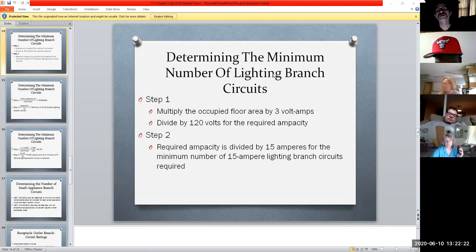So they have steps. Our big takeaway from this chapter is how we determine the minimum number of lighting branch circuits within our house. Our first step: we multiply our occupied floor area by 3 VA. If we have a 1,200 square foot house, we multiply it by 3 and come up with 3,600. We divide that by 120, which delivers our required ampacity. Step 2: we take that number and divide by our 15 amp circuit breakers to see what our minimum number of circuit breakers is going to be.